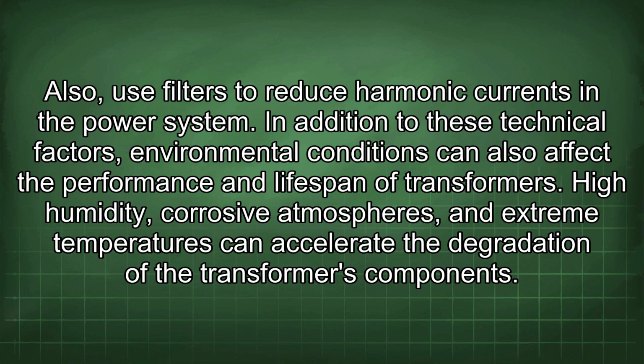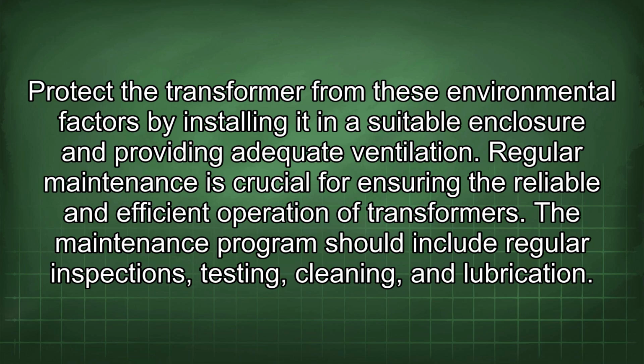In addition to these technical factors, environmental conditions can also affect the performance and lifespan of transformers. High humidity, corrosive atmospheres, and extreme temperatures can accelerate the degradation of the transformer's components. Protect the transformer from these environmental factors by installing it in a suitable enclosure and providing adequate ventilation.